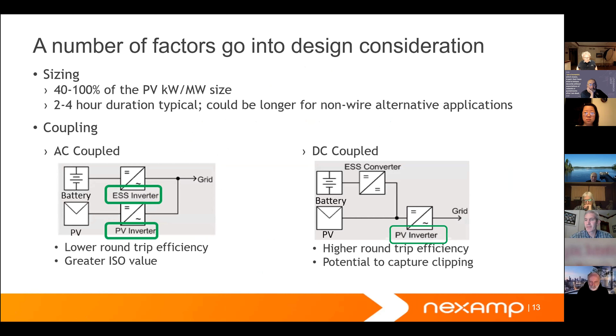And when we put it with the solar project, we can design it one of two ways. We can make it AC coupled, where you put in 2 inverters, and that allows you to charge from the grid, or you can just put in 1 inverter that goes out to the grid. There are benefits in terms of efficiency, losses, and value to the grid versus not, so it depends on the situation and the services you're providing, and you might have a different design.